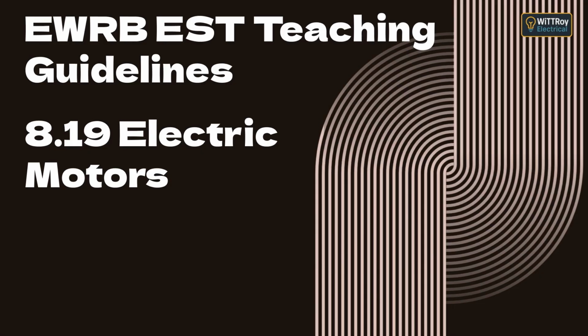Topic G. Starting methods for three-phase motors. Now let's move to Topic G. Starting methods. When a motor first starts, there is no back electromotive force, EMF, so it draws a large inrush current, often 6 to 8 times its full load current. To reduce this, different starting methods are used. Let's go through the main ones.